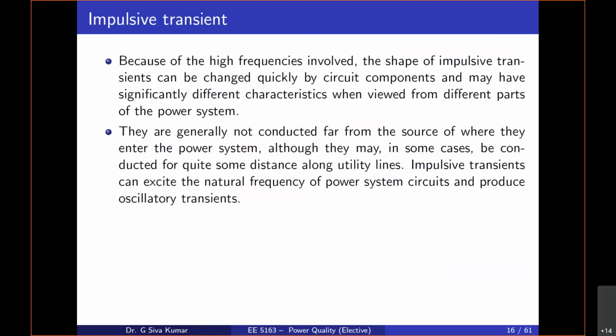Wherever we measure the inception, or wherever the lightning phenomenon occurs, it has a different magnitude as you go downstream to other distribution systems, due to the inductive and capacitive elements. There is a delay in the circuit - the transmission of a fault may be at light speed, so we cannot sense it, but the impact with respect to magnitude will vary.